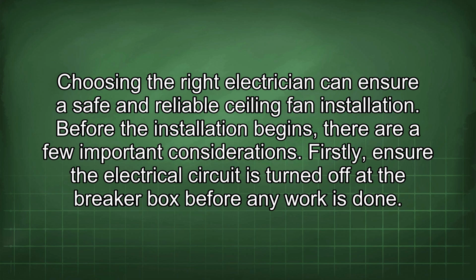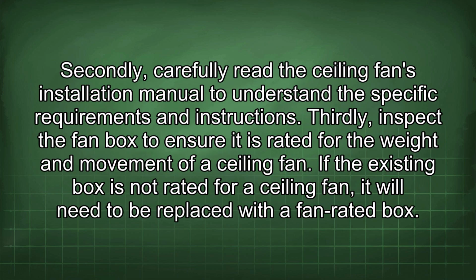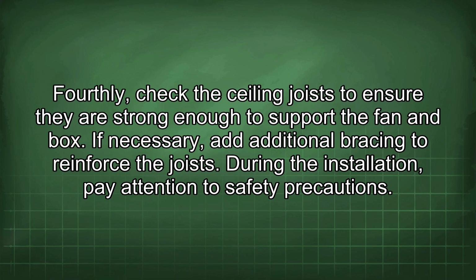Before the installation begins, there are a few important considerations. Firstly, ensure the electrical circuit is turned off at the breaker box before any work is done. Secondly, carefully read the ceiling fan's installation manual to understand the specific requirements and instructions. Thirdly, inspect the fan box to ensure it is rated for the weight and movement of a ceiling fan. If the existing box is not rated for a ceiling fan, it will need to be replaced with a fan-rated box. Fourthly, check the ceiling joists to ensure they are strong enough to support the fan and box. If necessary, add additional bracing to reinforce the joists.